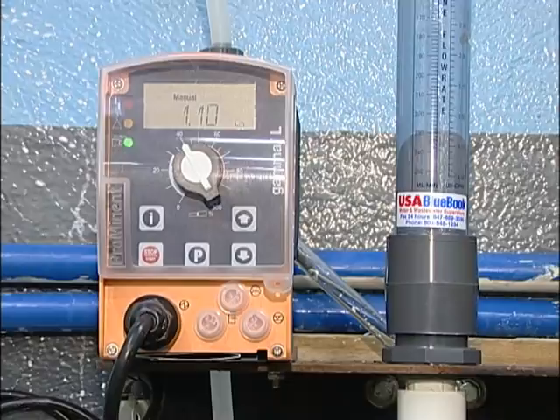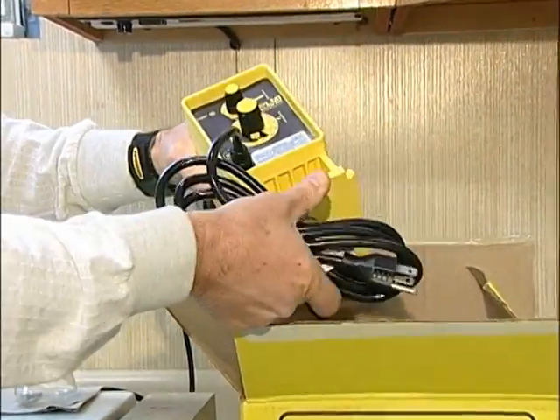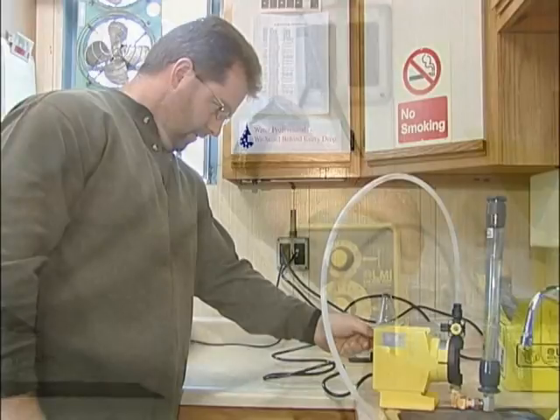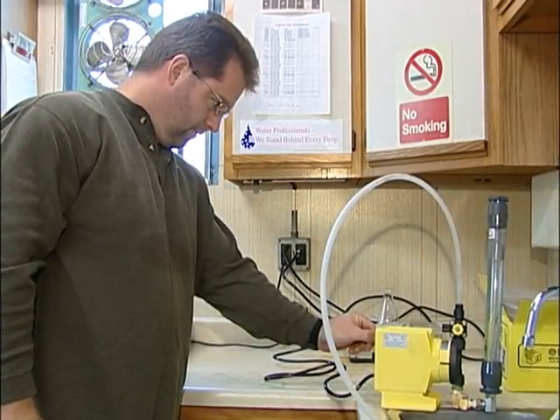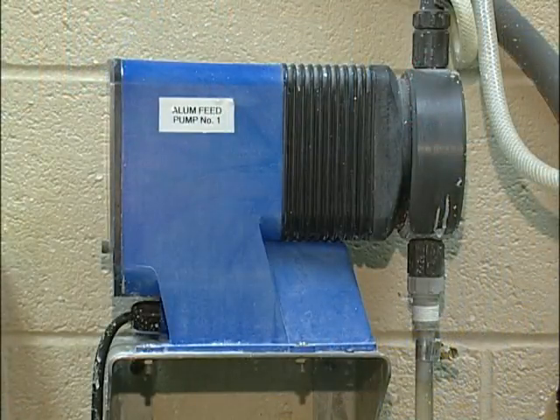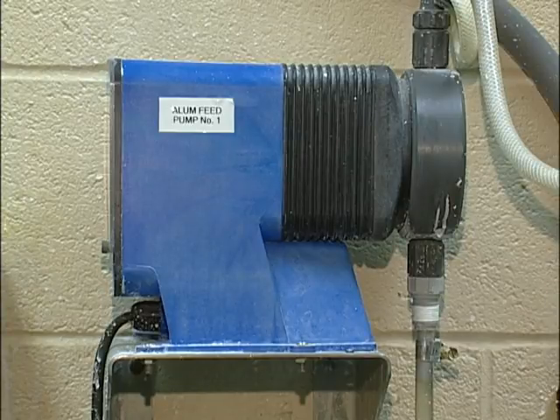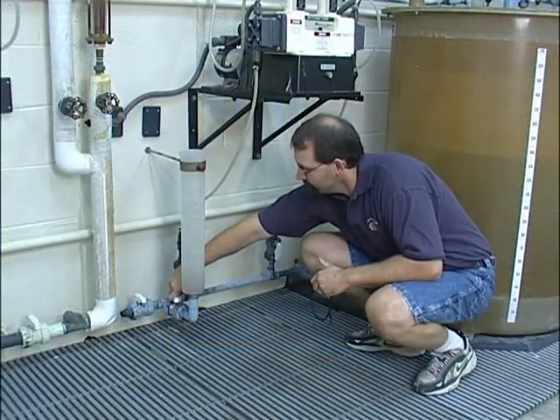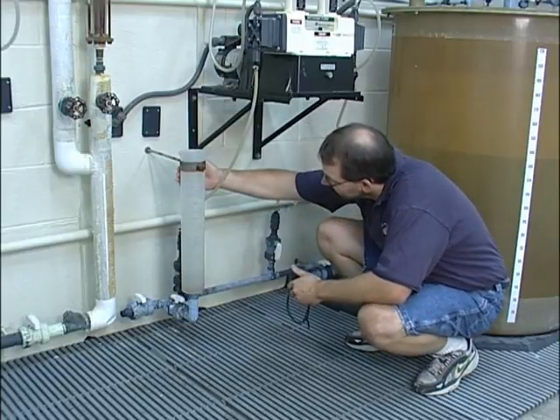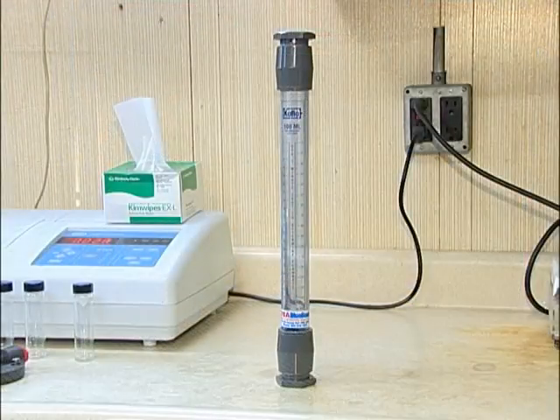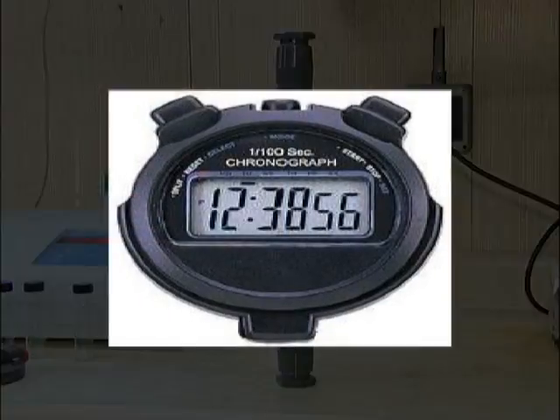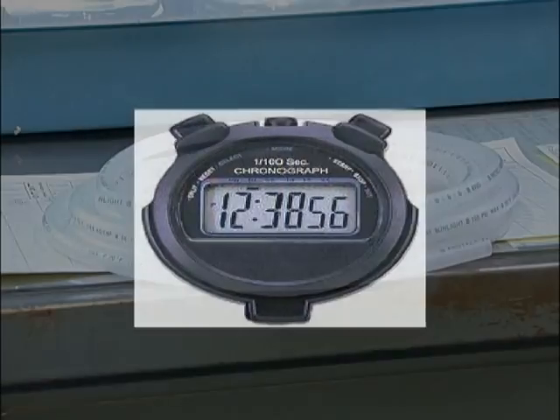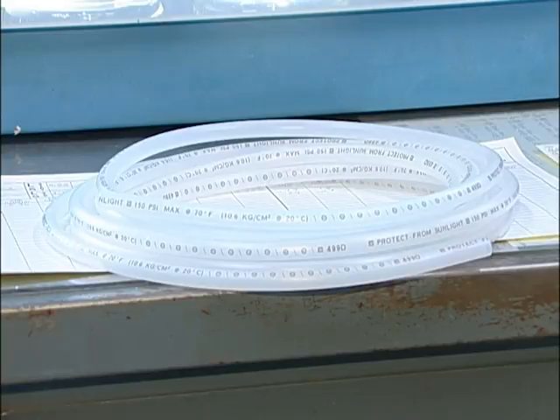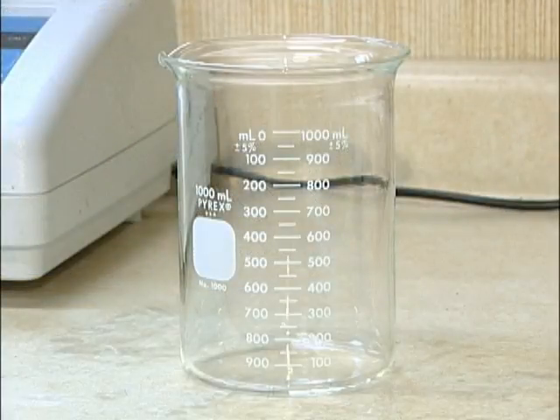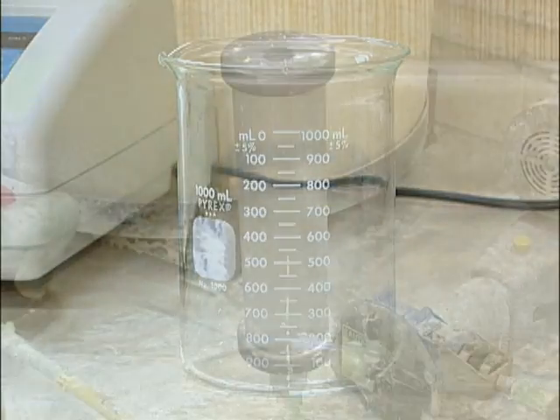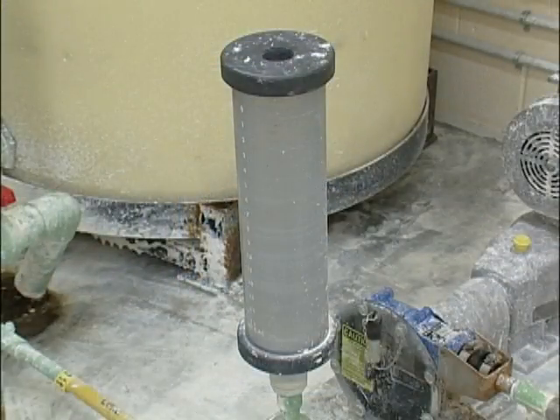A pump calibration should be done on pumps when they are new, as well as periodically after they are in service to verify their delivery rates. Sometimes pump delivery will vary as the parts age and weaken. To do a pump calibration, the following equipment is necessary: a calibration tube of proper size, a timer or stopwatch, tubing to connect the pump to the chemical supply it will be pumping, and a beaker to receive the chemical if a calibration tube is not plumbed into the feed line.